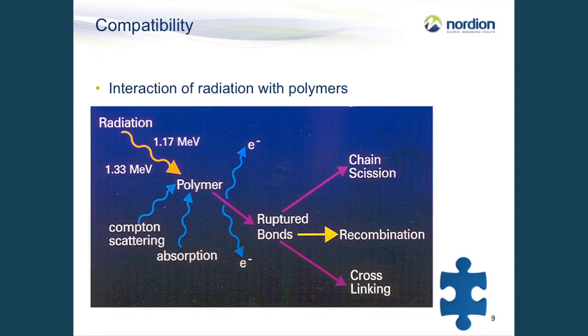In some cases, these changes can have a beneficial effect. For example, cross-linking can make materials stiffer or more flexible and result in better mechanical properties. In some cases, though, the radiation can lead to embrittlement, discoloration, or deterioration. The effect will be dependent on both the polymer and the dose. When designing with sterilization in mind, consider looking at radiation compatibility of the polymer as part of the design process.